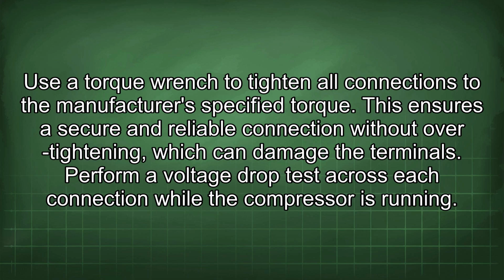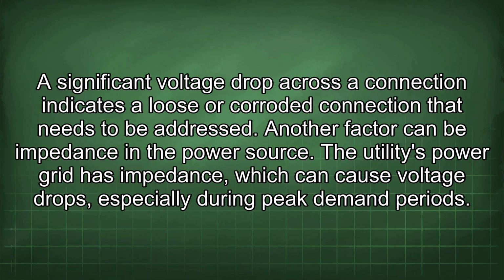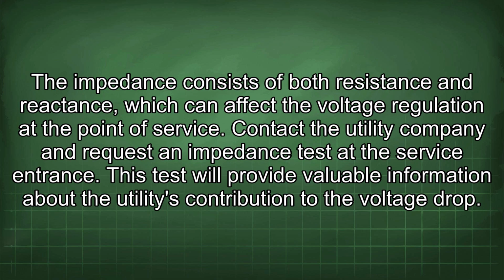Perform a voltage drop test across each connection while the compressor is running. A significant voltage drop across a connection indicates a loose or corroded connection that needs to be addressed. Another factor can be impedance in the power source. The utility's power grid has impedance, which can cause voltage drops, especially during peak demand periods. The impedance consists of both resistance and reactance, which can affect the voltage regulation at the point of service. Contact the utility company and request an impedance test at the service entrance.